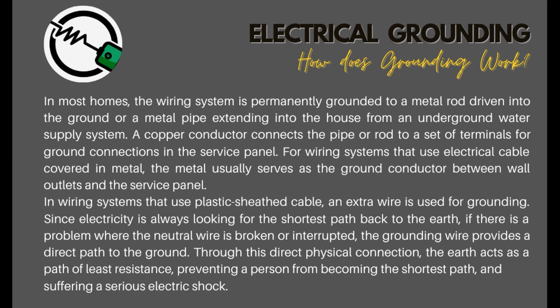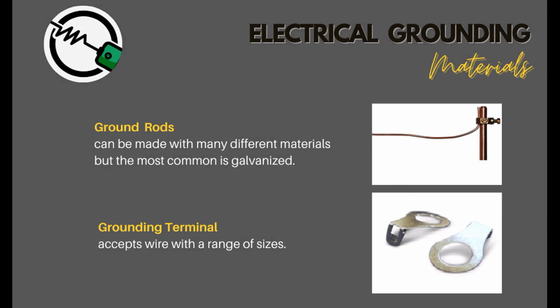Since electricity is always looking for the shortest path back to the earth, if there is a problem where the neutral wire is broken or interrupted, the grounding wire provides a direct path to the ground. Through this direct physical connection, the earth acts as a path of least resistance, preventing a person from becoming the shortest path, and suffering a serious electric shock. Electrical grounding materials. Ground rods. Ground rods can be made with many different materials, but the most common is galvanized. Grounding terminal. Grounding terminal accepts wire with a range of sizes.